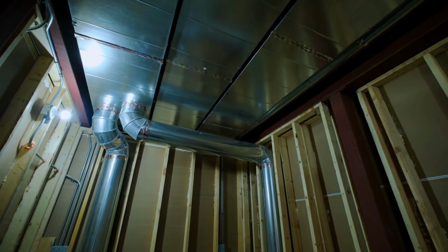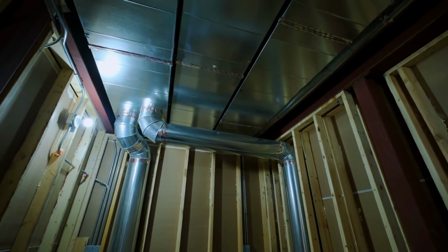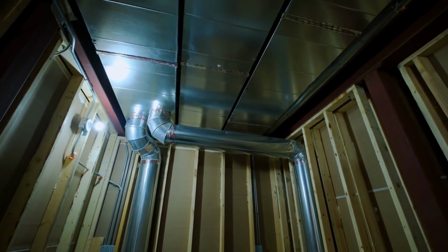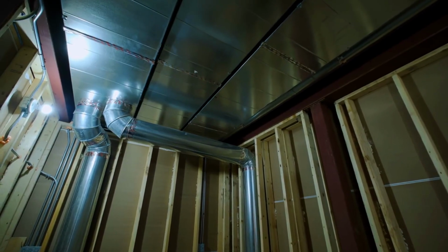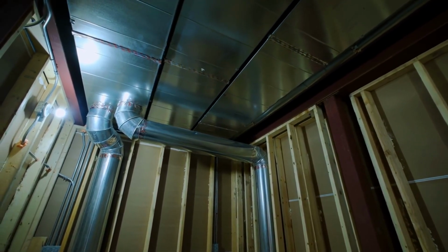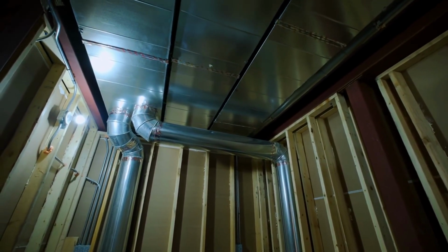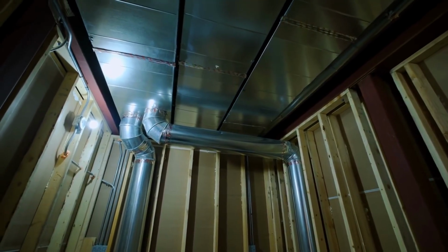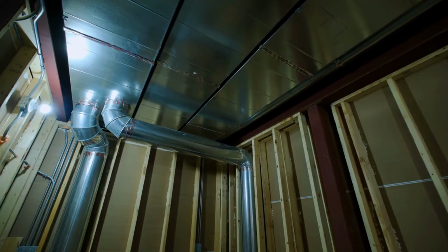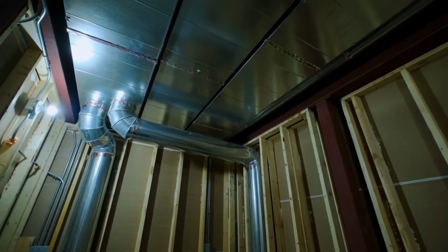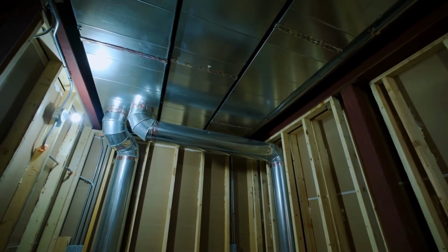HVAC for existing buildings with limited ceiling heights. In major modification or substantial reconstruction projects in existing buildings where classrooms have limited ceiling heights, different systems are used. 1. If classrooms are served by DX vertical unit ventilators or VRF units and decoupled custom DX-DOAS central heat pump units, corridors should have a dedicated DX multiple zone variable air volume system or a dedicated single zone constant air volume unit.